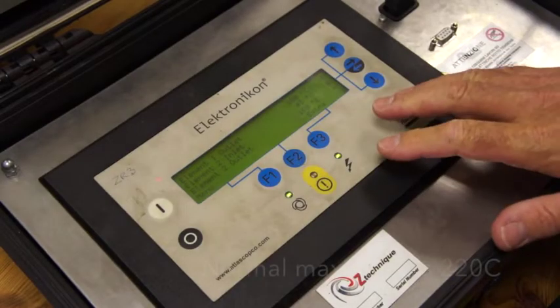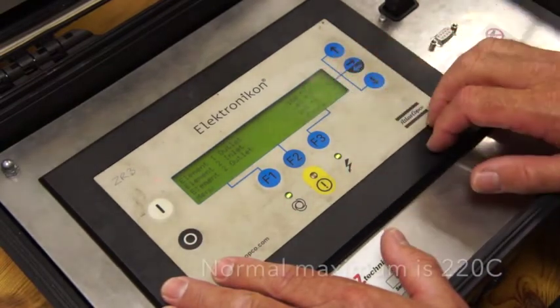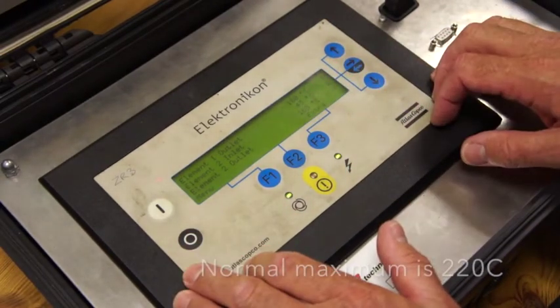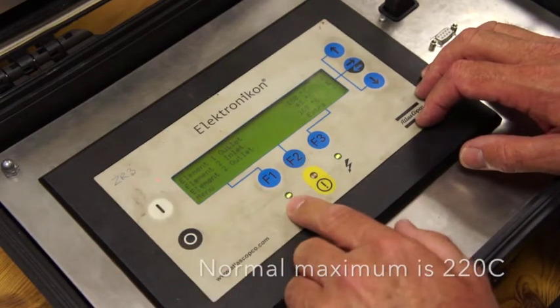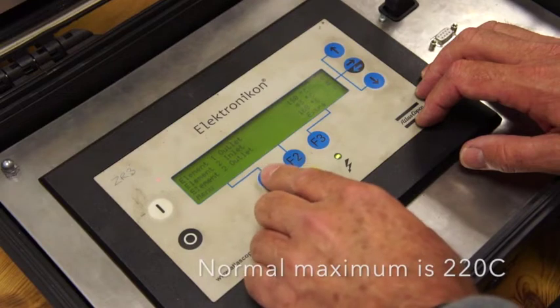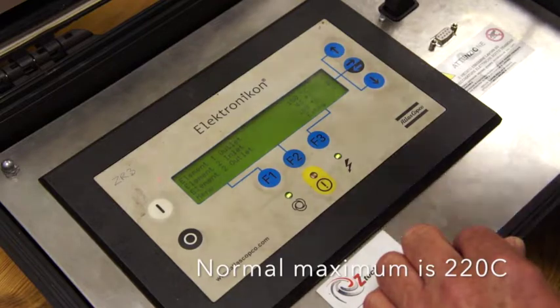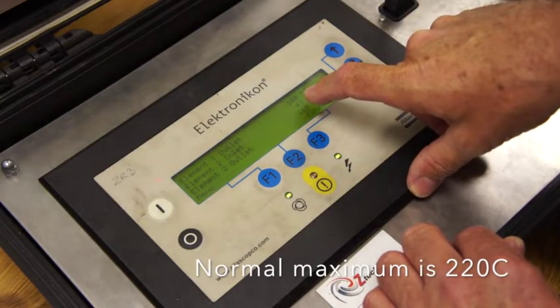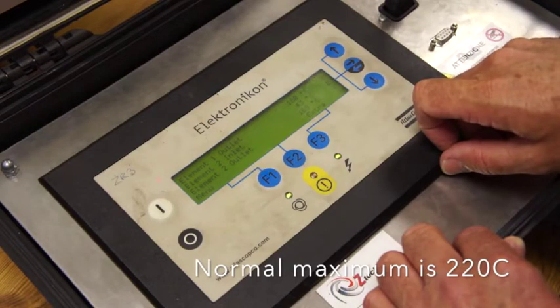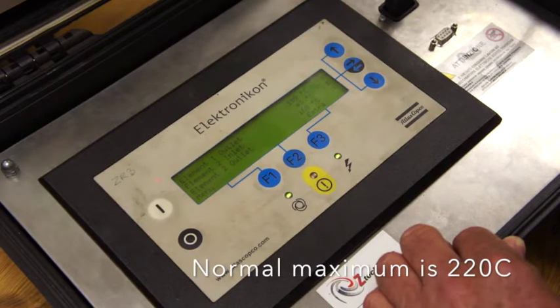For this example I want to show a high temperature in the elements and the consequences. The compressor is running. We've gone F1 into measured data and come down. Now I'm going to increase the temperature of the element 1 outlet.